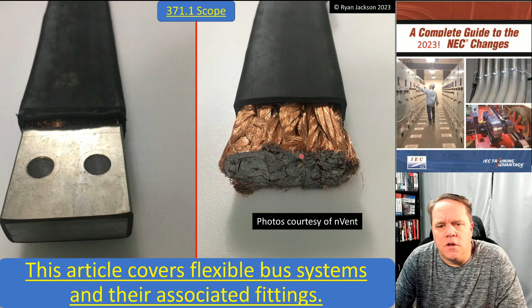This is what it looks like from the outside, and you can see the bolt holes that match the ANSI configurations for switchgear. If you were to cut it open, you'd see it's actually built of super fine stranded conductors, and that's what gives it its flexibility. Here is a cross section, and you can see the little angel hair size pieces of wire sticking out. There you go, it's a flexible bus.